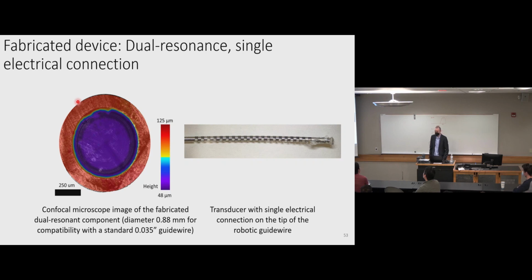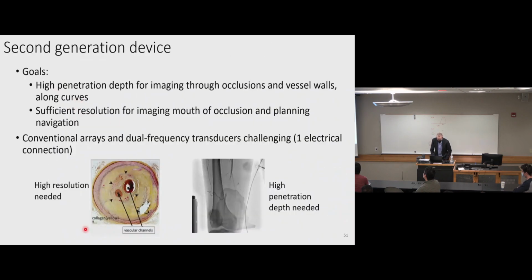The challenge is, in some cases, you can't get it beyond the occlusion, and maybe this may not be visible from this one here because I'm only showing the 2D slice. But in some cases, the occlusion that you're trying to get through is very tortuous. So it's not necessarily like once you get the tip in here, then it's a straight, smooth path all the way through. So it's helpful to be able to see the tortuous nature of that channel before your device is pushing right up against it. And that can allow you to plan the trajectory if you have some complicated path that the steerable guide wire will need to take. Okay, thank you.